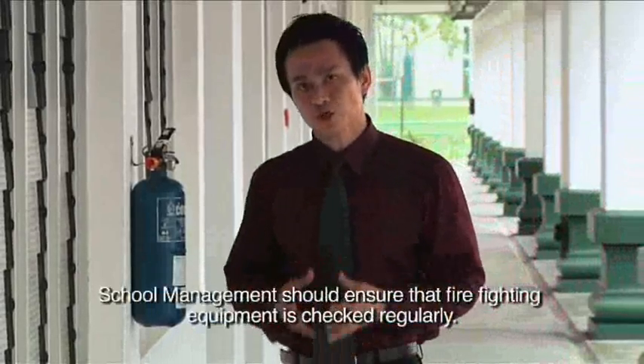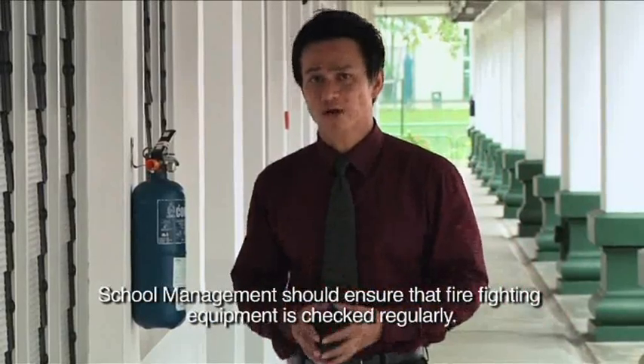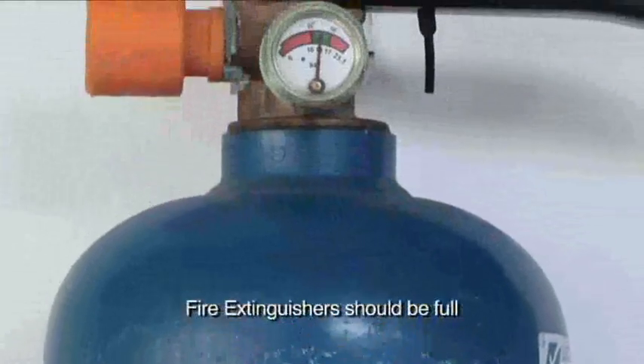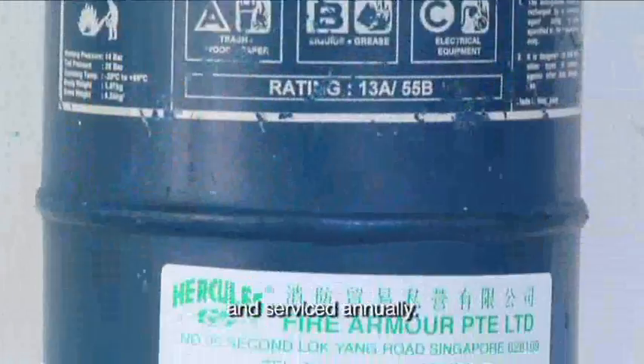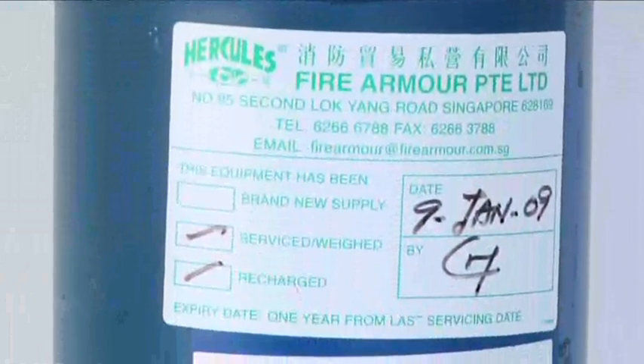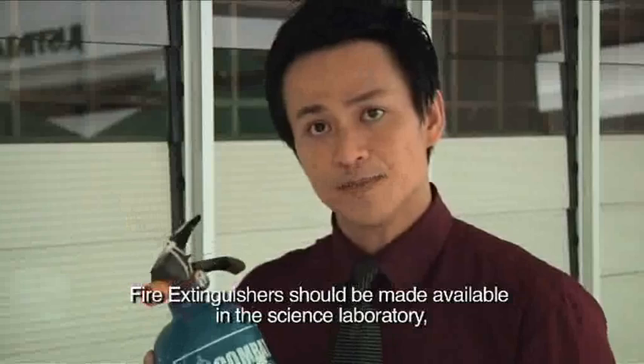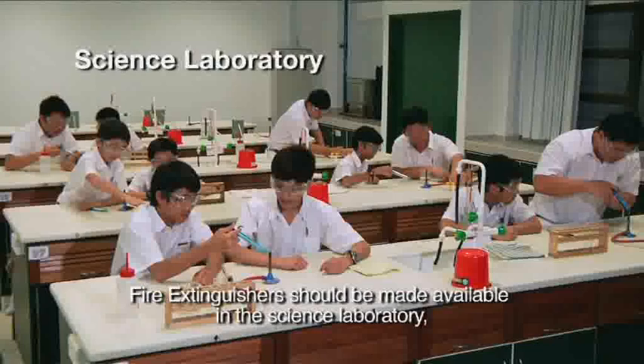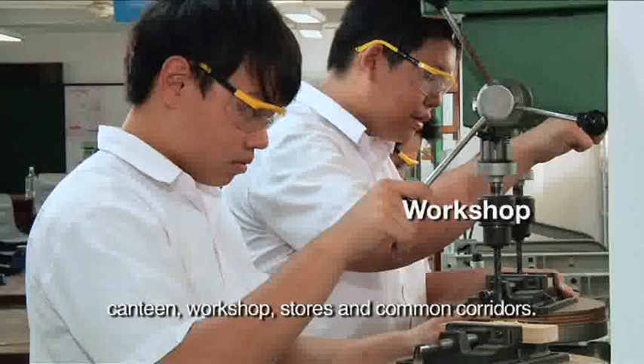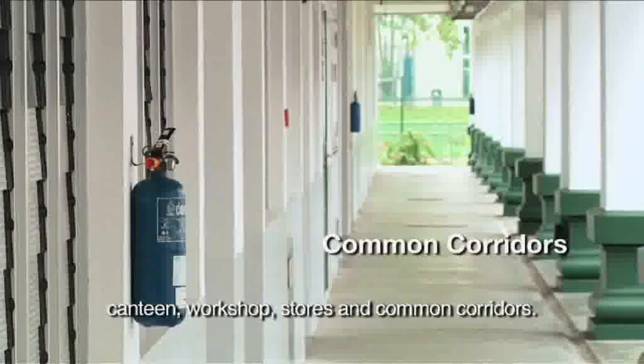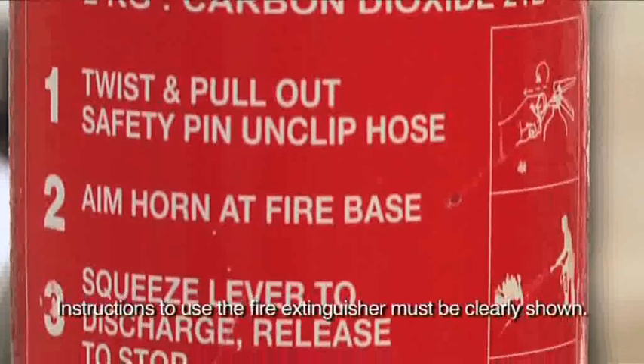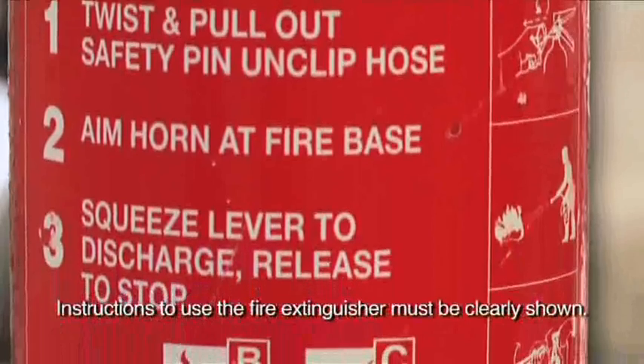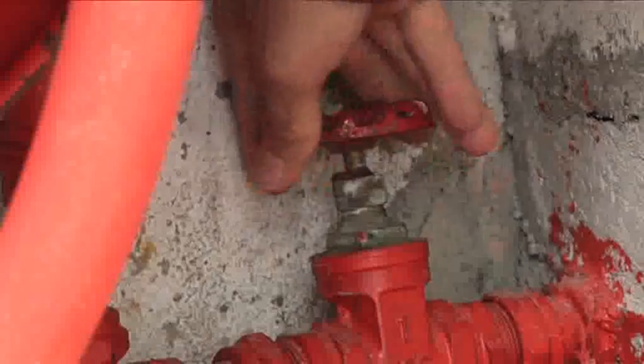School management should ensure that firefighting equipment is checked regularly. Fire extinguishers should be full and serviced annually. Fire extinguishers should be made available in the science laboratory, canteen, workshop, stores, as well as the common corridors. Instructions to use the fire extinguisher must be clearly shown.